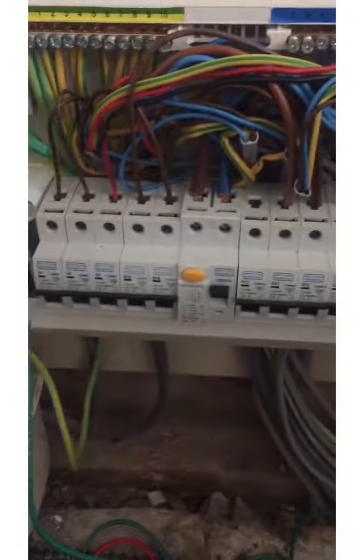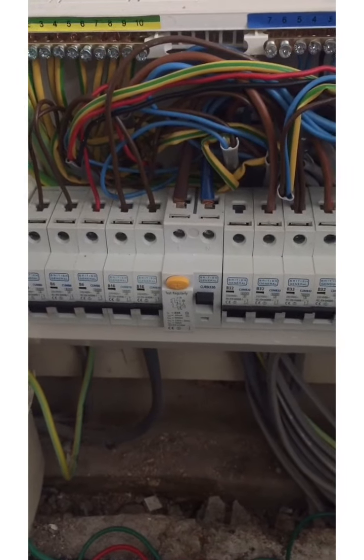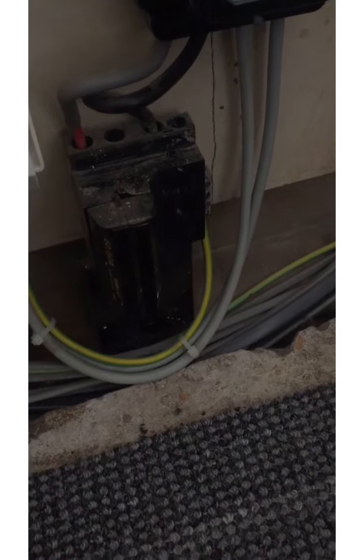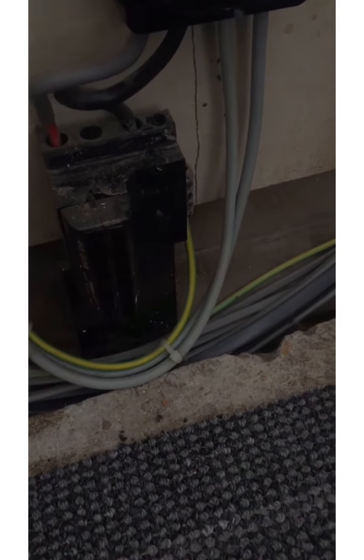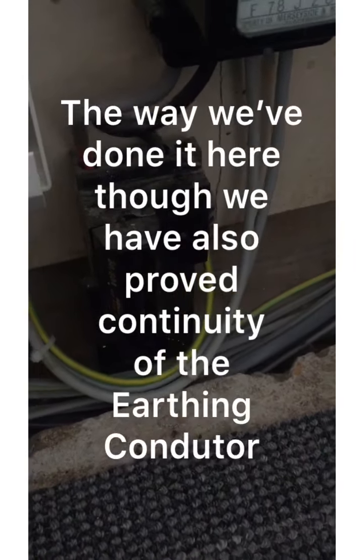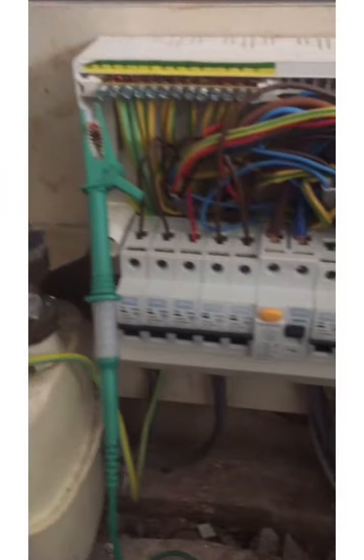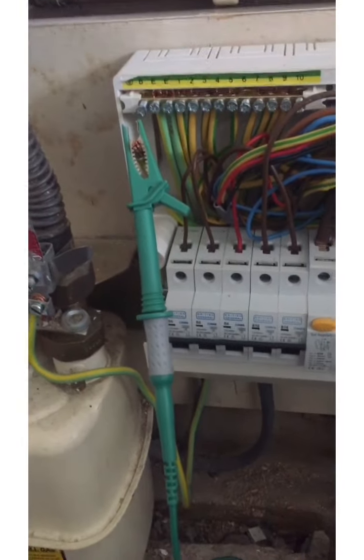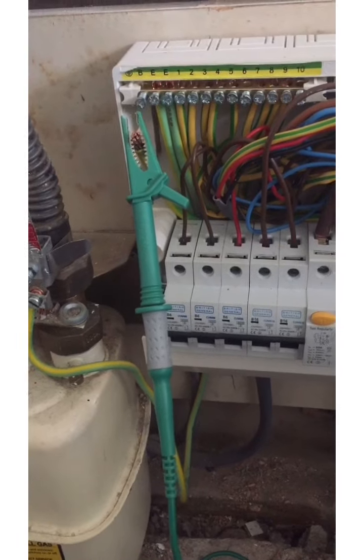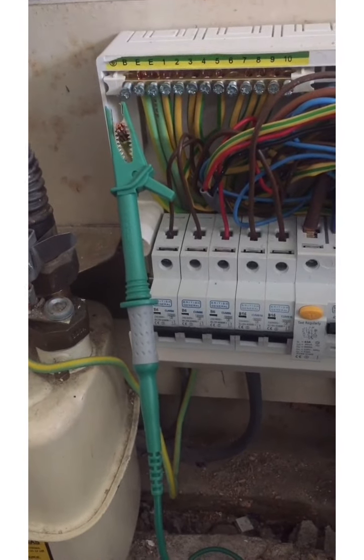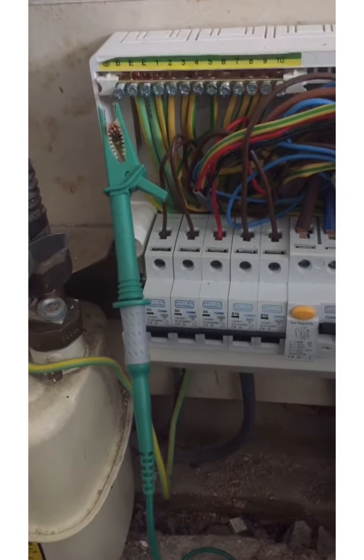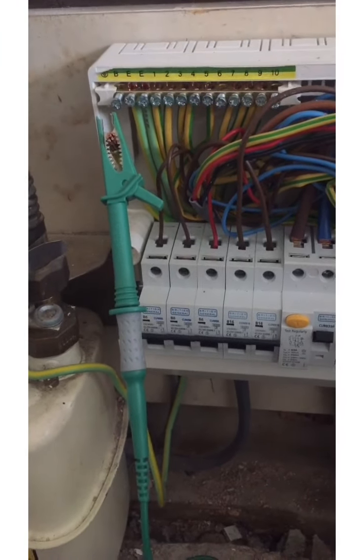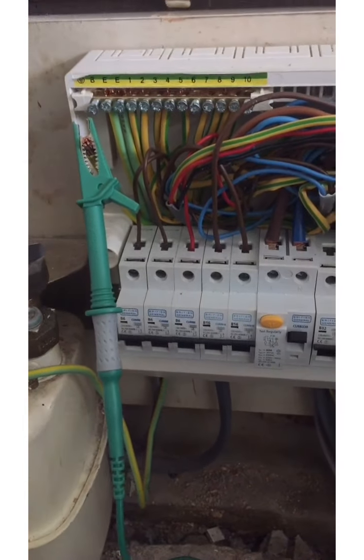I mean, it says in the guidance to disconnect. Well, you could disconnect it from the means of earthing and take the reading to the means of earthing. Well, the main point of it is that we don't have any parallel paths concerned. We're just testing that the earth fault loop impedance of the supply, independent of any parallel path through structural steelwork, etc., is bona fide.